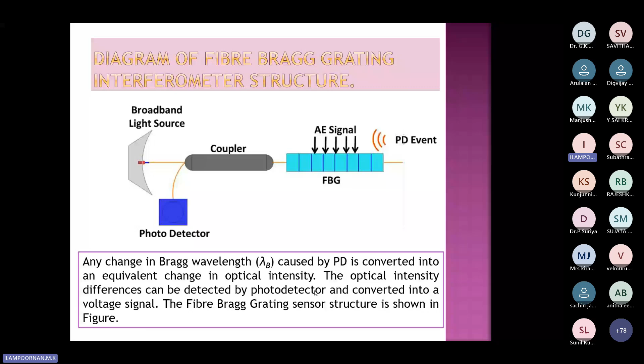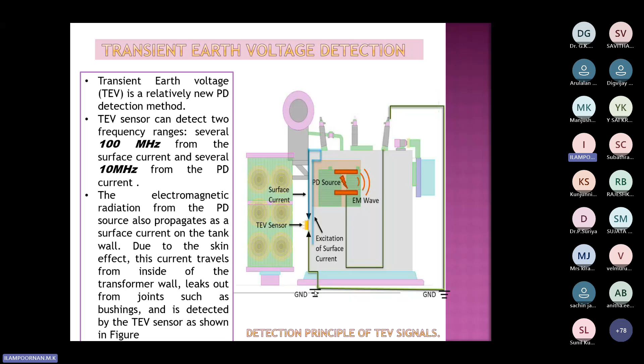Apart from that, you have transient earth voltage detection, which is understanding the electromagnetic radiation of PD through the tank. You put a sensor on the tank, and when the PD hits the tank from the other side, you try to triangulate by putting TEV sensors on the tank. Similarly, you have the core passing through the earth wire, and from that also you can understand how much is the PD.